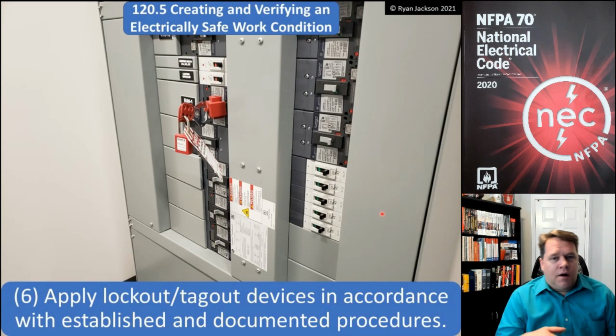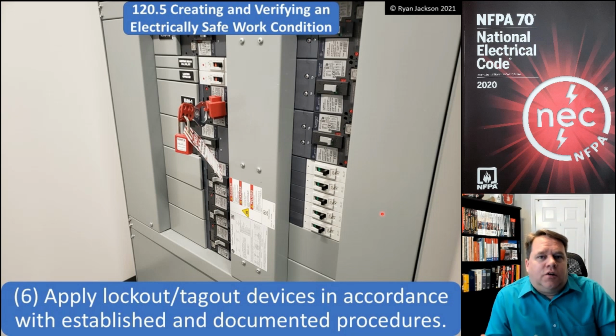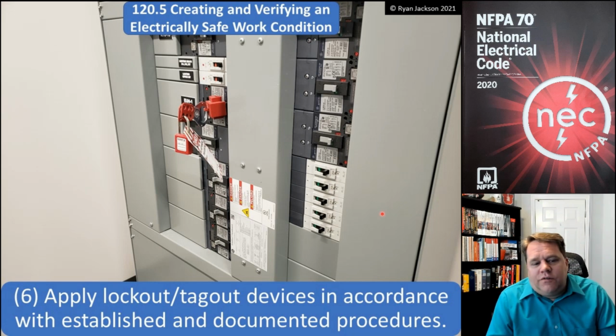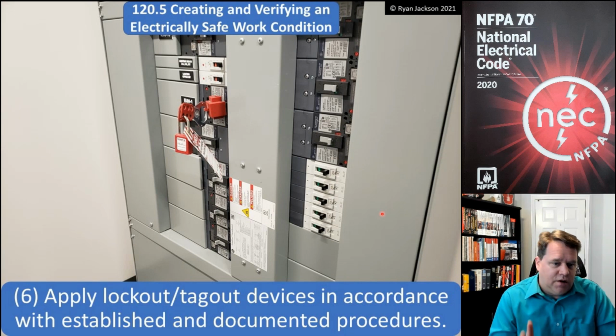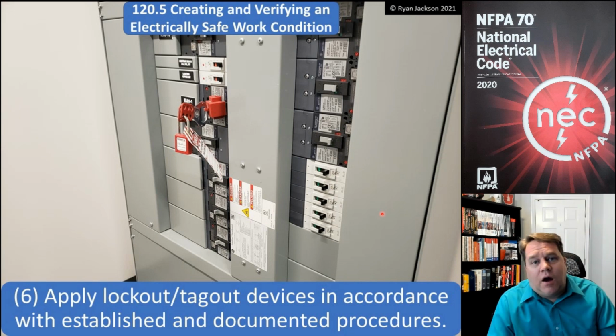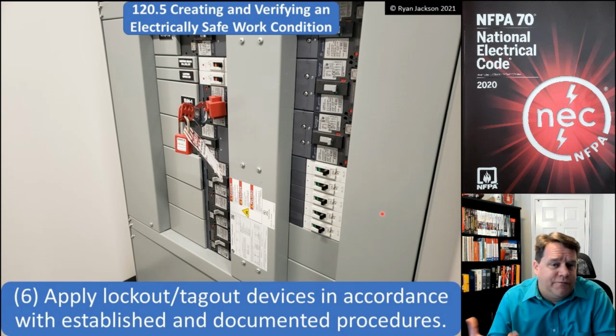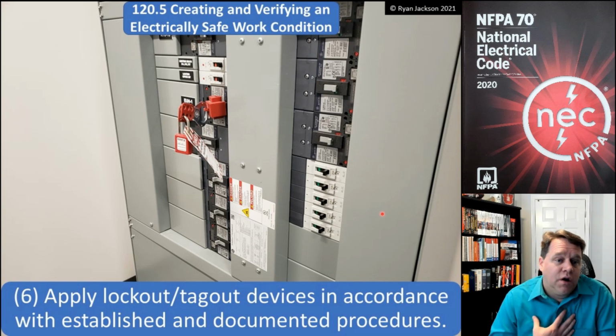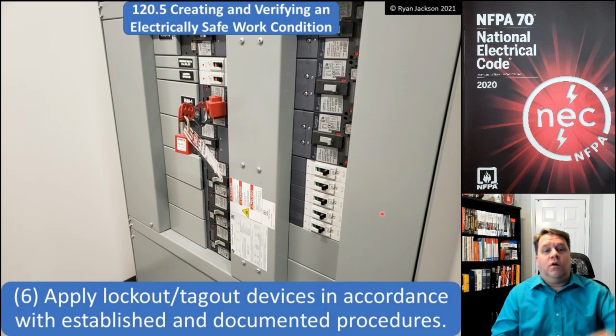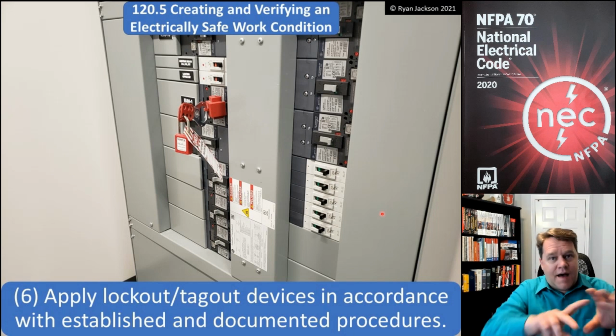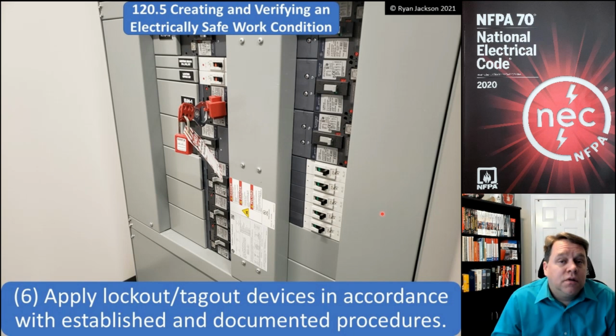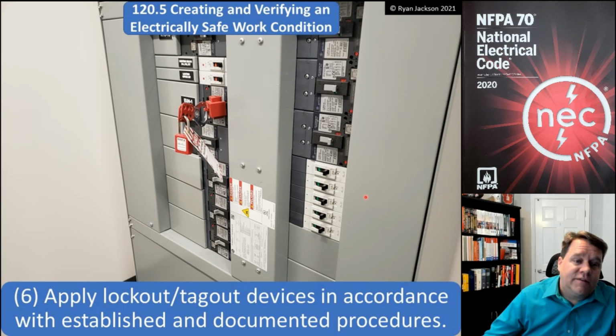Item 6. Now we need to apply a lockout or a tagout device in accordance with established and documented procedures. All right, so we say the phrase lockout, tagout, and we use that term a lot of times without even fully understanding what it means. For years, I thought that lockout, tagout was the lock and the tag, and it's not. You know what a tagout is? It's pretty much like a cable tie. That's a tagout.